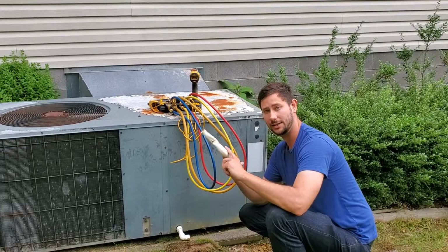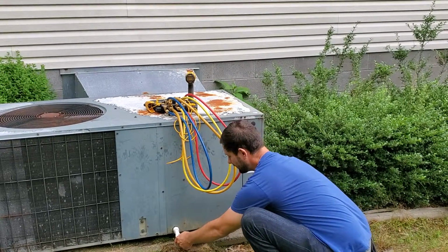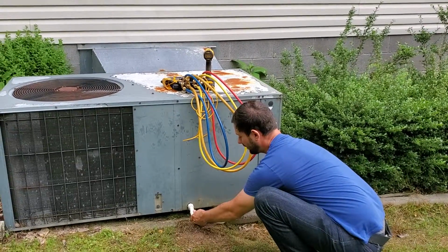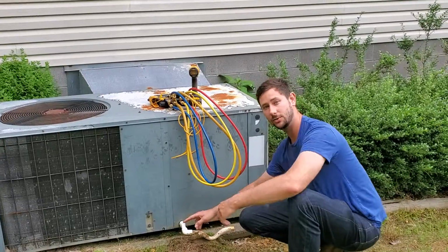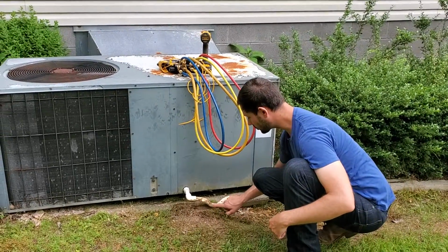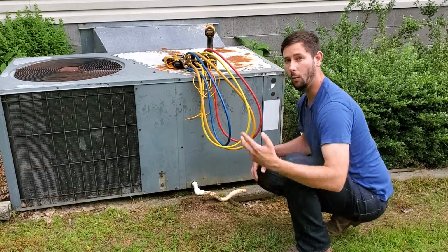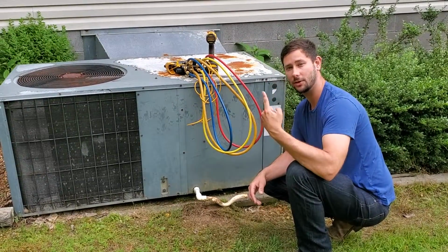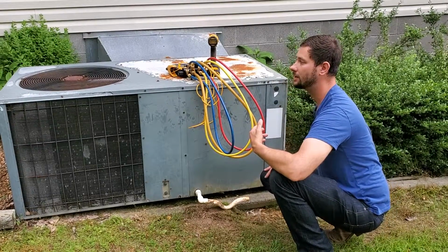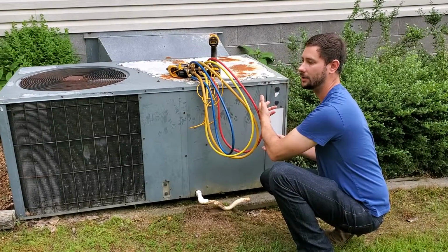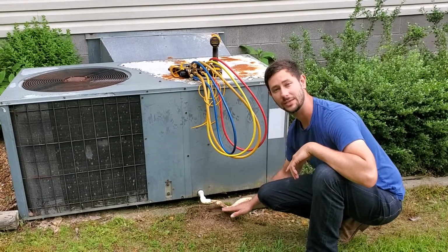So to efficiently install this trap here that I found when I arrived on the service call, I just basically placed this in the actual drain pipe leading from the evaporator drain pan. And what that's going to do is, if you'll take a look, this trap that's in here is going to fill up with water, and it's basically going to keep one of two things from happening. The first is, if this drain was to run into a main waste pipe or a main drain line in your plumbing, it would suck back an odor if you didn't have a trap.